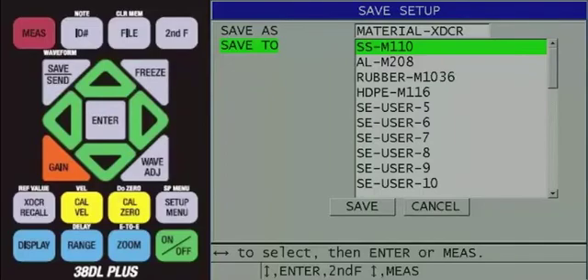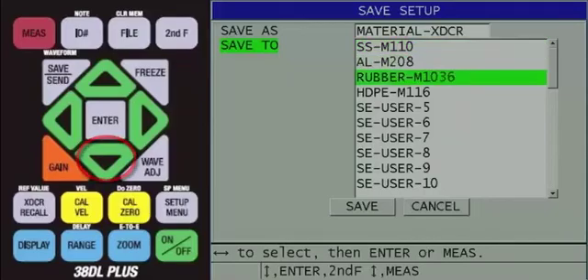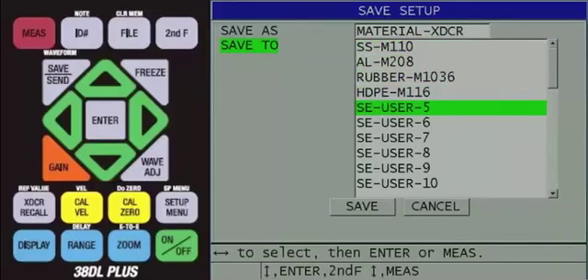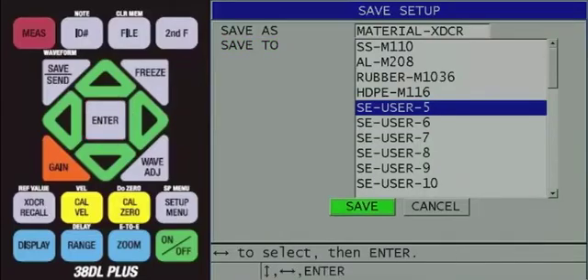Now, the save to line will be highlighted, and you can choose where to save the custom transducer setup. Use the arrow keys to highlight an available SE-User setup number. Then press the enter key so save is highlighted, then press the enter key again.